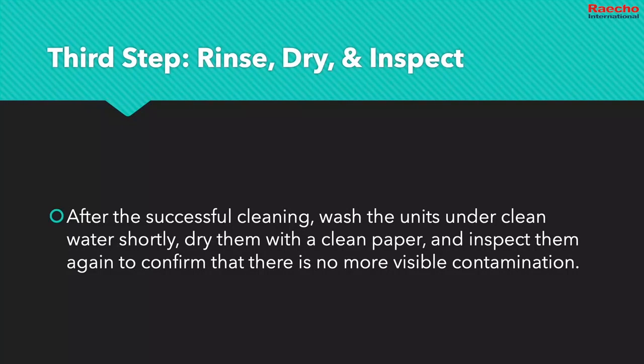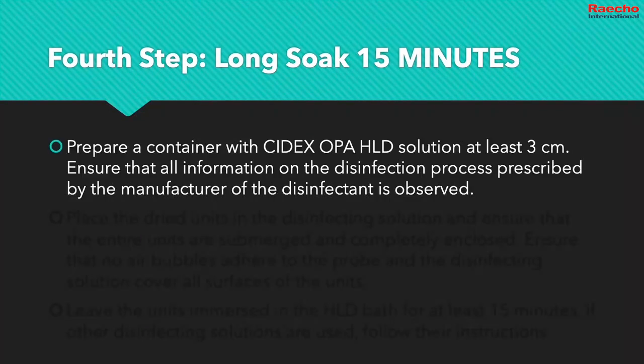After the successful cleaning, wash the units under clean water shortly, then dry them with a clean paper or cloth and inspect them again to confirm that there's no more visible contamination. The fourth step is a long soak in a high-level disinfectant. Prepare a container with CIDEX OPA HLD solution, at least 3 centimeters deep.